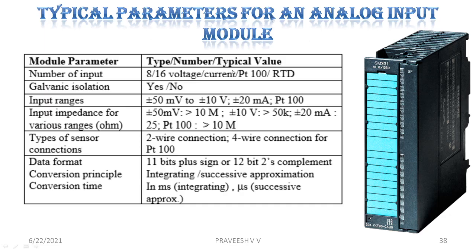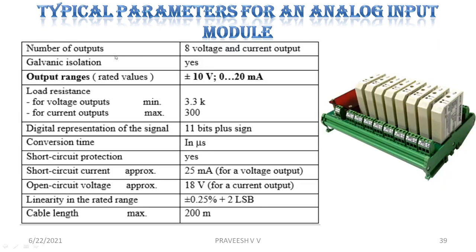Here are typical parameters for input and output modules — analog input module and analog output module parameters. These include: number of inputs/outputs, galvanic isolation, input range voltage, input impedance, sensor connections, data format, output range, load resistance, digital representation, conversion time, short-circuit protection, short-circuit current, open-circuit voltage, linearity, and maximum cable length. These are the output specifications normally provided per module.